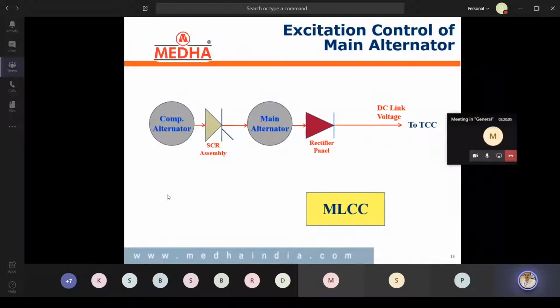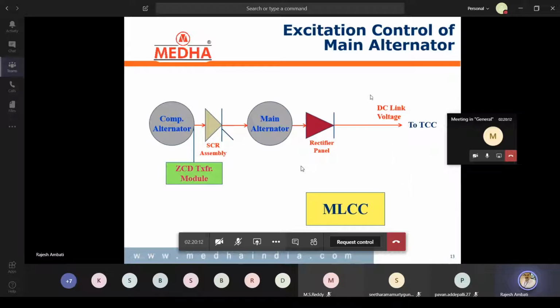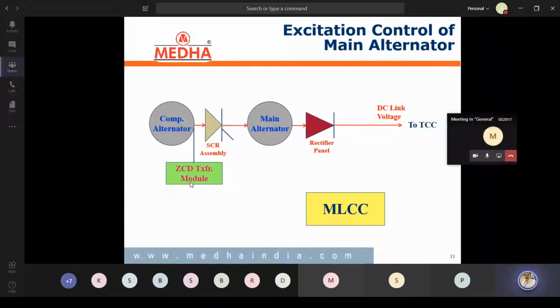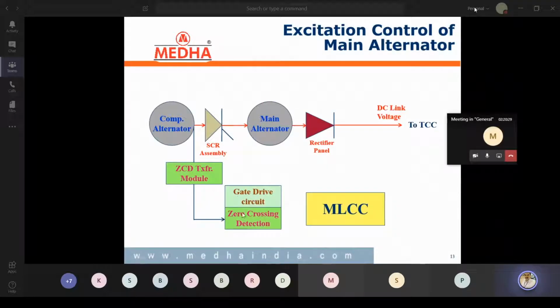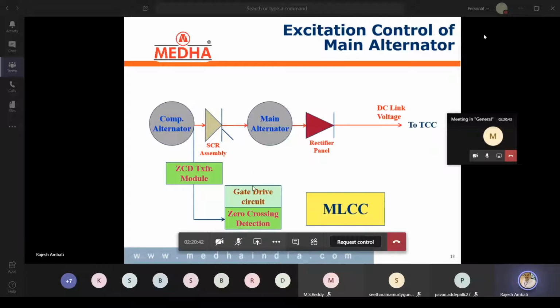which is available inside the LCC, for controlling purposes it first has to monitor zero crossing detection. For that purpose there is a ZCD transformer module which steps down 100 to 13.5 volts. If the input voltage is 100, then the output becomes 13.5, and that low voltage signal comes to one card, this MGD ZCD card, which is available inside the LCC unit. Like MLCC, this is also one more card. In this card, there are two sections: a zero crossing detection section and a gate drive section.